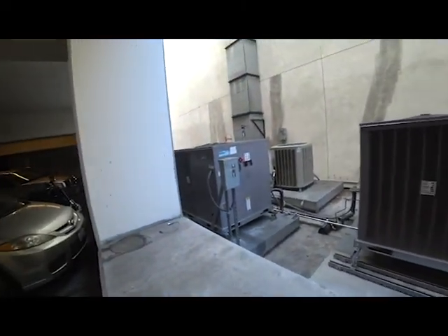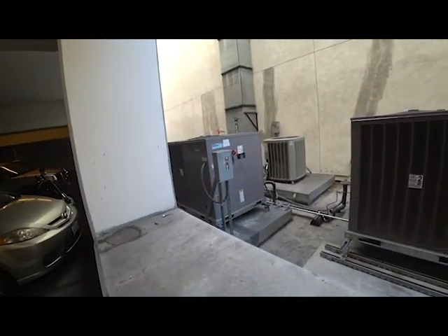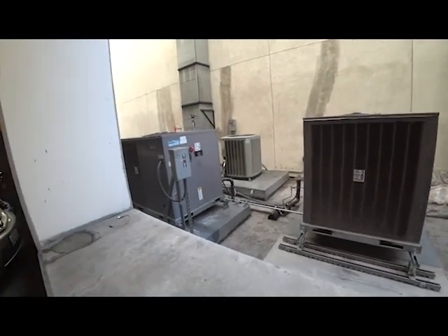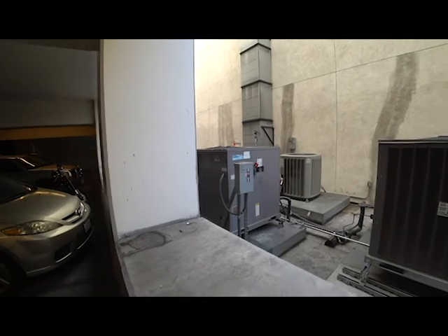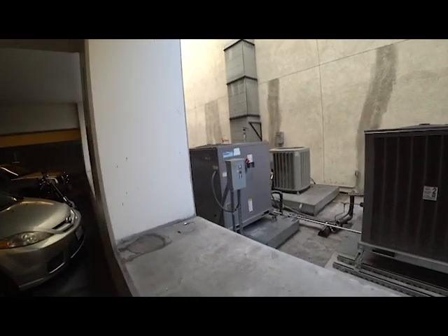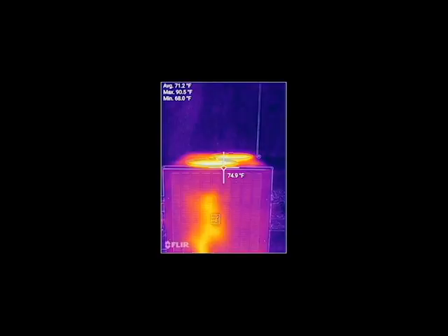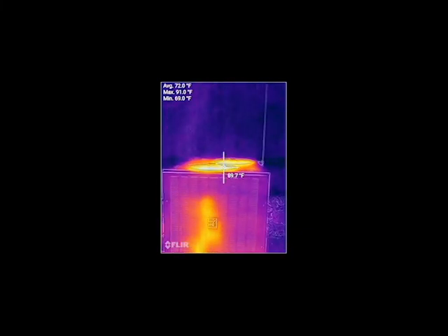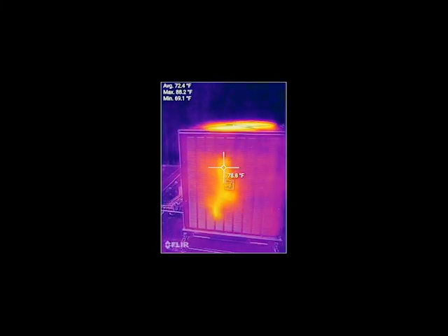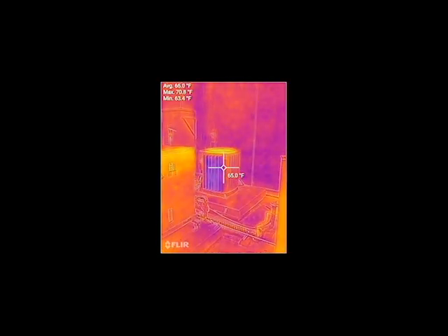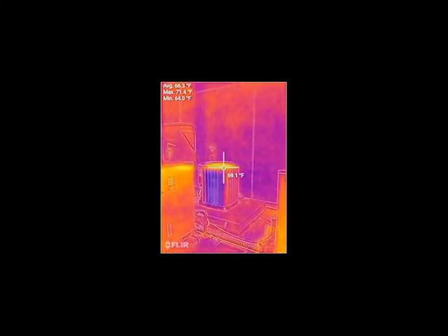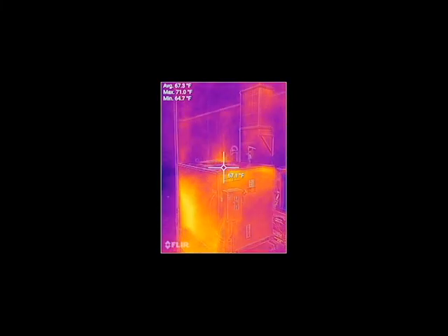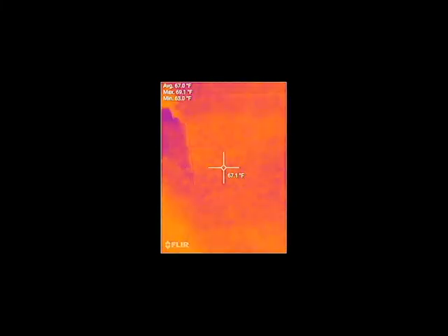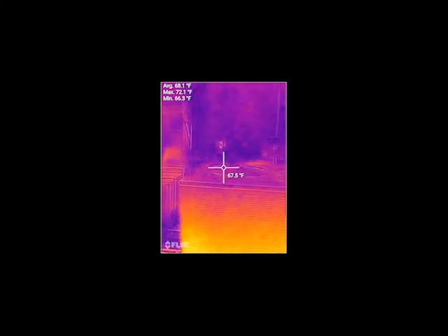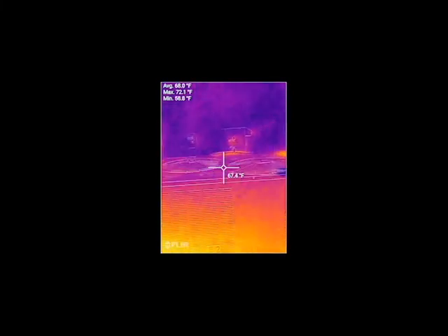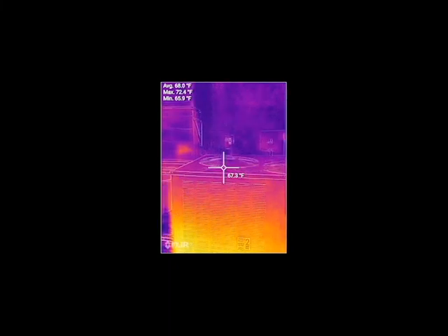Okay, so 2 of the 3 units were started up by Climatech, and after an initial loud start, they both sound good, but this 3rd unit here, which I believe serves the front, is not operating. So we're starting to see some temperature differential. This unit has kicked into a cooling mode. Same thing over there, we're seeing a differential now. This one is not doing anything right now. Nothing happening yet. We'll wait to see what happens.